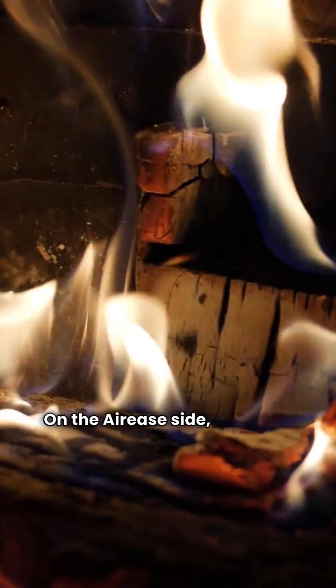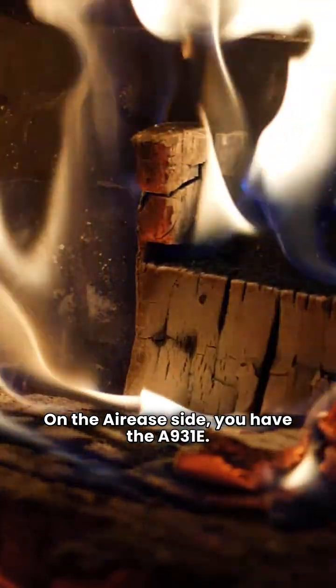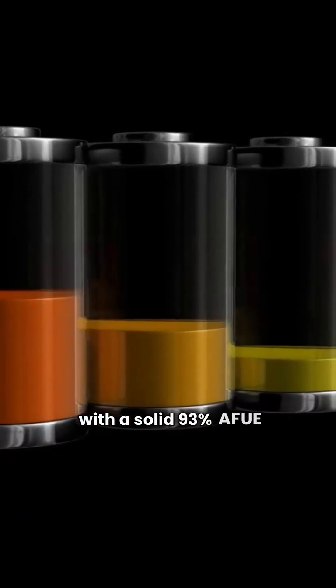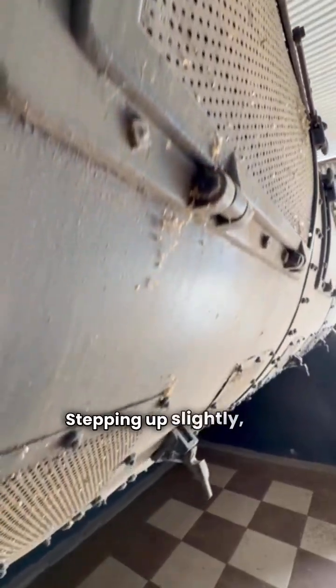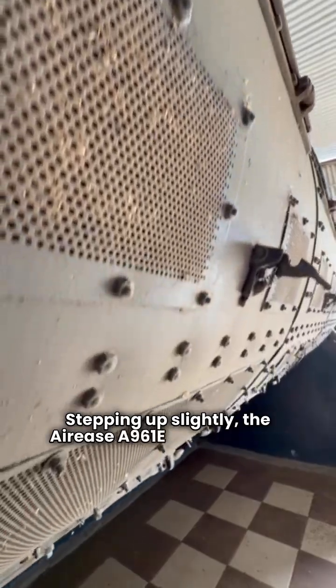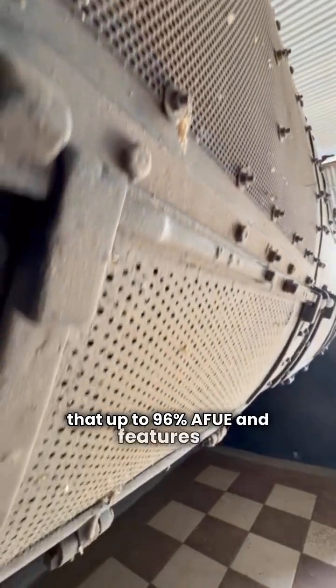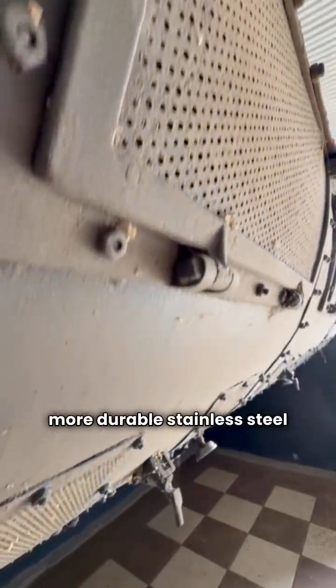On the Airease side you have the A931E. It's a single-stage fixed-speed furnace with a solid 93% AFUE efficiency. It uses an aluminized steel primary heat exchanger. Stepping up slightly, the Airease A961E model bumps that up to 96% AFUE and features a more durable stainless steel heat exchanger.